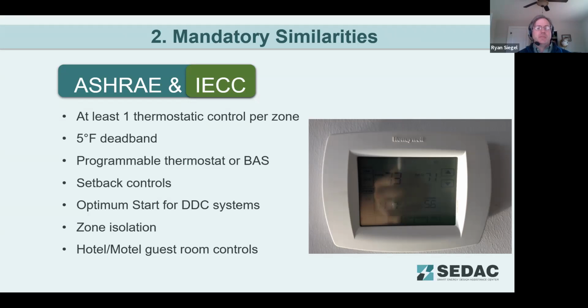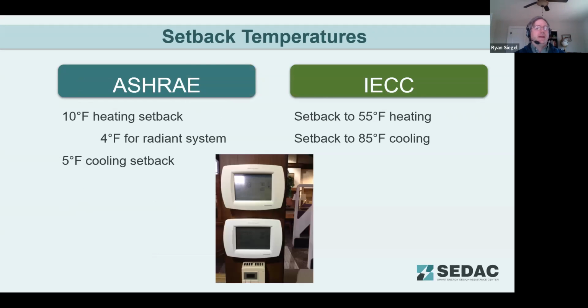And also they have a lot of similarities in their setback requirements. We definitely need to make sure that we do have at least one thermostat control per zone. And Sean mentioned the 5-degree deadband goes up to 7 if you're having a system that goes occupied standby, programmable thermostats and setbacks and zone isolation. So again, this is the same across both ASHRAE and IECC. One area that's substantially different is the setback temperature, where ASHRAE specifies a 10-degree heating setback on the heating side and a 5-degree cooling setback.